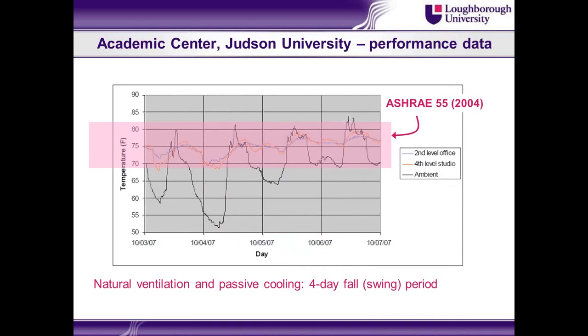How much thermal mass can you say in each of these buildings is available to the occupants' view angle in the space? How much thermal mass is available to the occupants? Is it like two times the floor area? Essentially, all of the ceiling and all of the walls. I haven't done the calculation in terms of what that is in floor area. It'd be interesting to do that. All of the ceiling area is what we aim for. The walls are less important because the view factor is up towards the ceiling, and especially when you're sitting side by side, it's making sure that the ceiling is cool. So, a lot essentially, but I can't quantify.